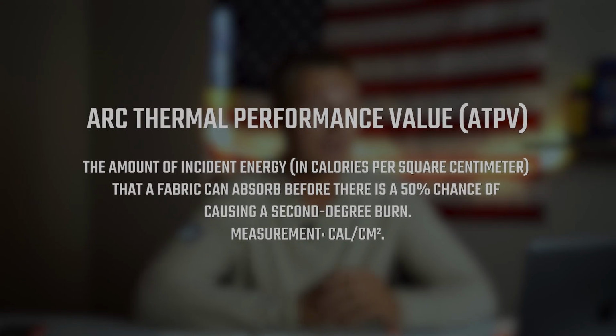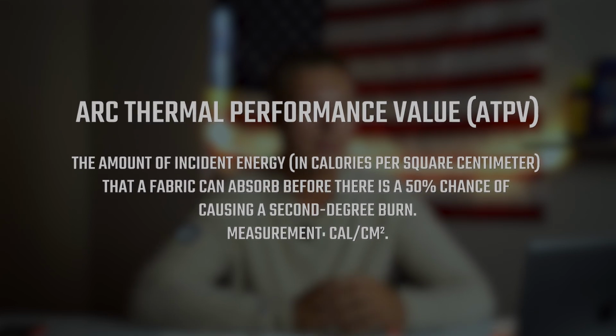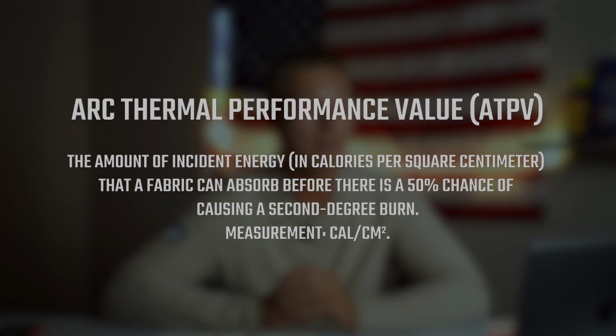Now, because I'm not smart enough to just spit this off the top of my head, really what the arc value is rated off is the amount of incident energy in calories per square centimeter that a fabric can absorb before there is a 50% chance of causing a second-degree burn. To me, to you, that might sound like gibberish. What I do know is that for the most part, for us linemen, we have to wear a minimum of Cat 2 and an arc rating of 8.7 calories per square centimeter. That's kind of the base level of FR that we need to wear on the outside for protection.